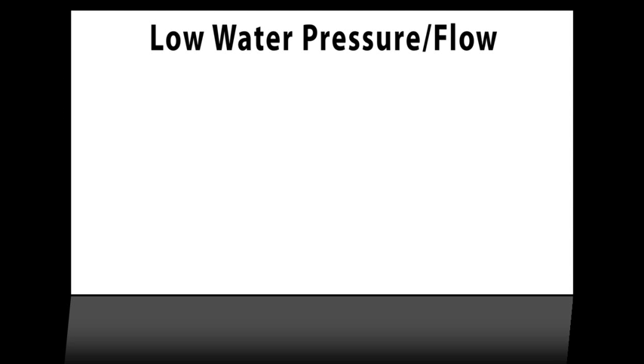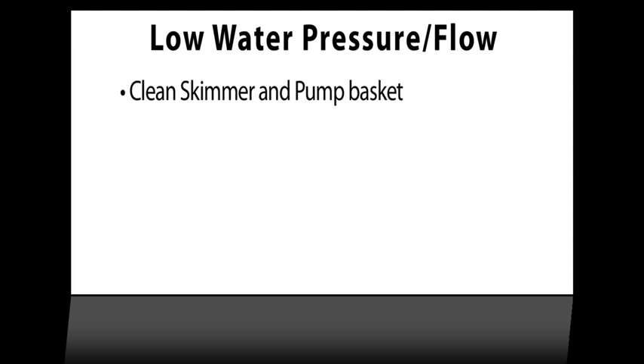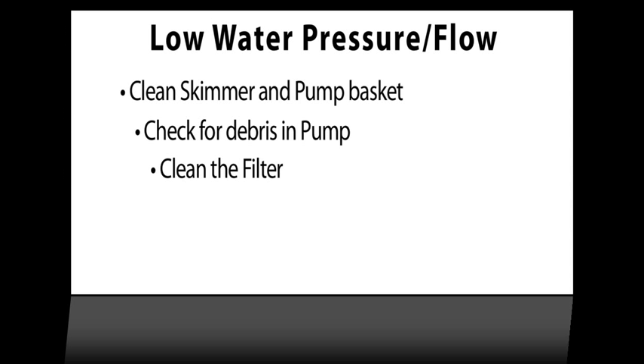Low water pressure or low water flow can cause the heater to turn off. Clean the pool skimmer basket and the pump inlet basket. Pull the pump inlet basket out of the pump and check for debris in the pump's impeller. Clean your pool filter — depending on the type of filter you have, you can clean or temporarily remove the cartridge, or give your earth filter a bump-down or backwash.